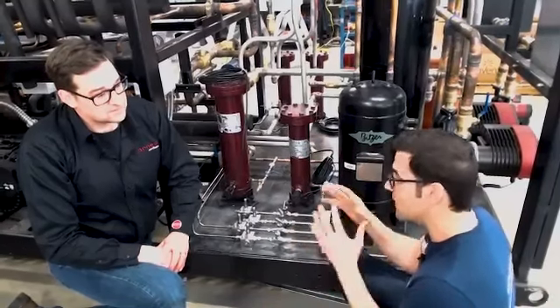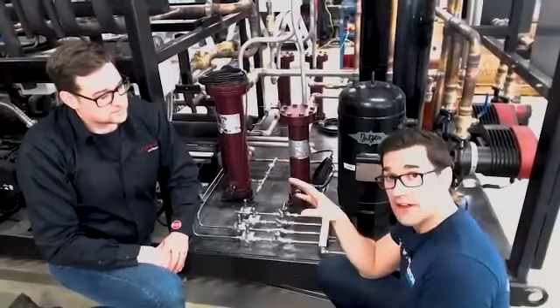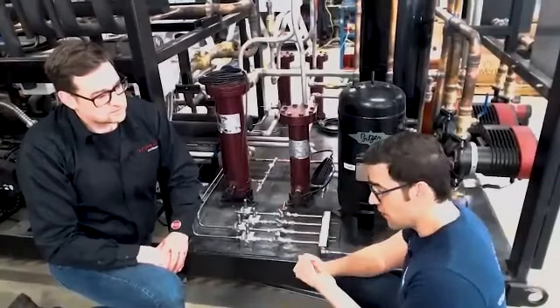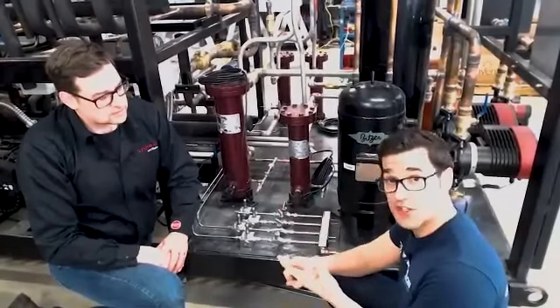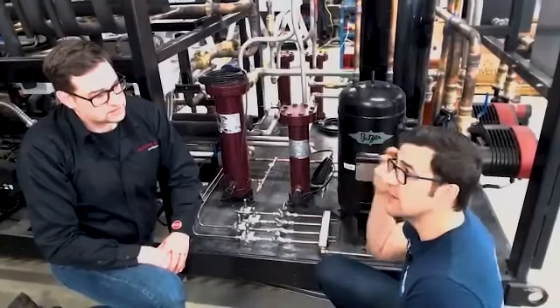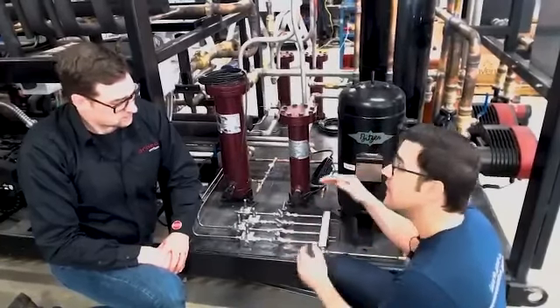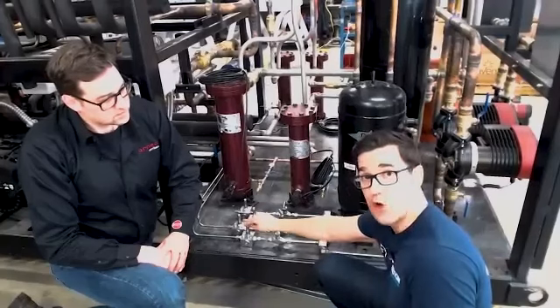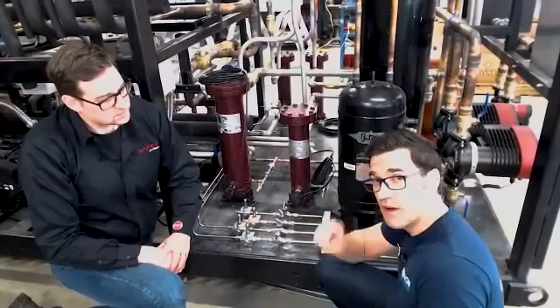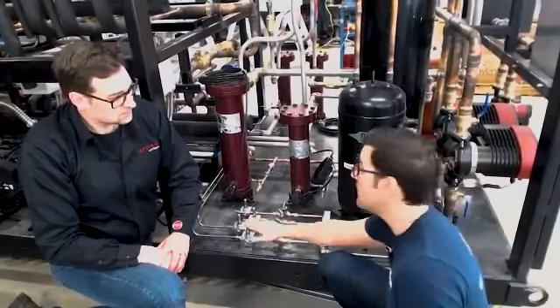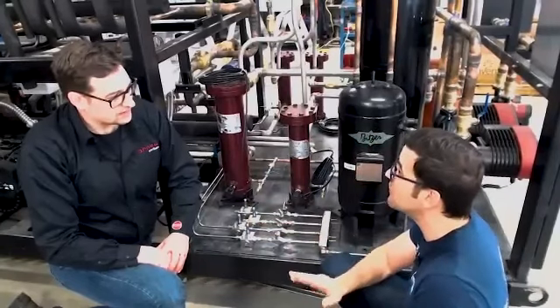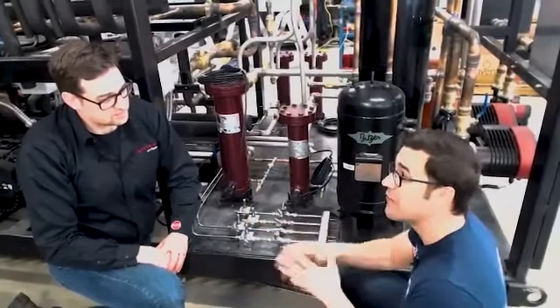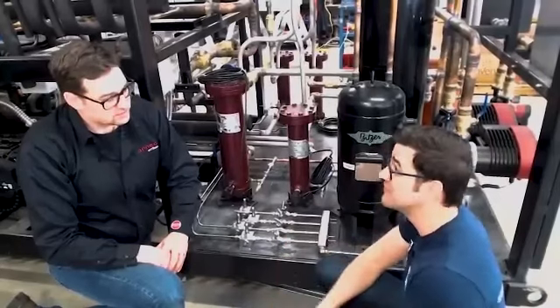You want to go back and understand all those pressures: oil pressure, flash tank pressure, suction pressure, and really start to think about what's happening inside when one of these block solenoids opens. You want to understand each component, because when this opens, it's going to change the pressure somewhere else. Understanding that sequence of operations is key.